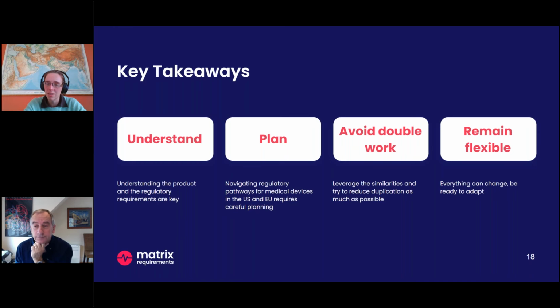First thing, and that's the same for all devices, is what is my intended use? What are my claims? Do they fit within this legislation? Is it a software? Is it a medical device? Once we know that, then you have to create the documentation that is required depending on the classification of your software. There are specific standards about the life cycle of software, standalone software or software integrated in a medical device. So for example, IEC 82304 is one to look at when you have a standalone software.